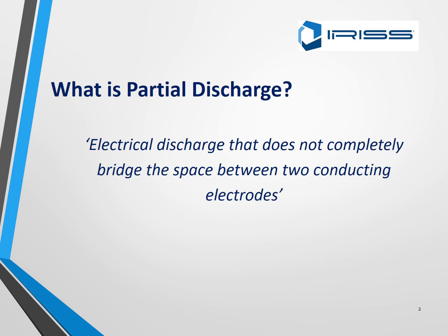What is PD? PD is an electrical discharge that does not completely bridge the space between the two conducting electrodes. The discharge may be in a gas-filled void, or in a solid insulating material, in a gas bubble in a liquid insulator, or around an electrode in a gas — known as surface tracking or corona.